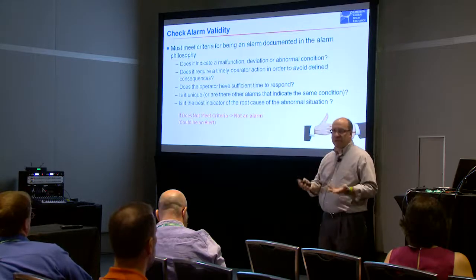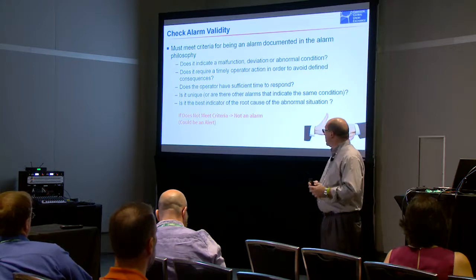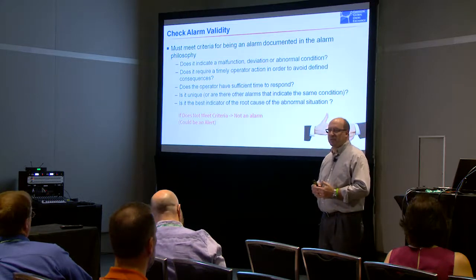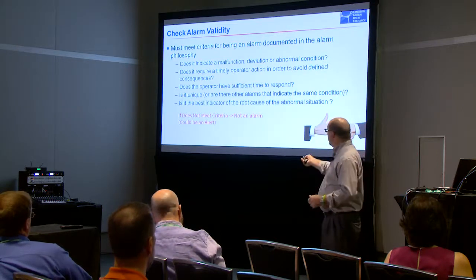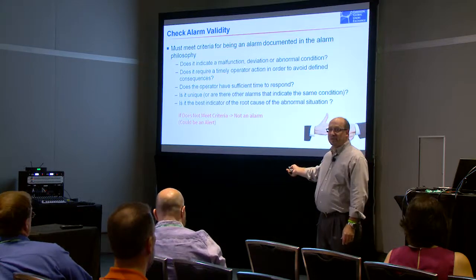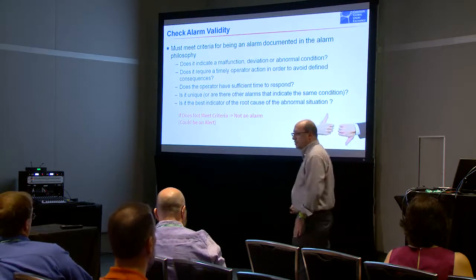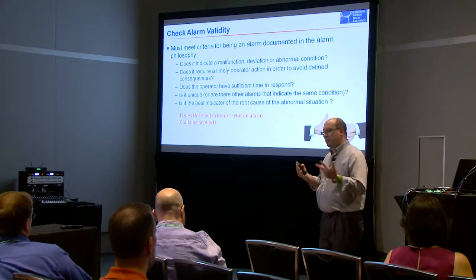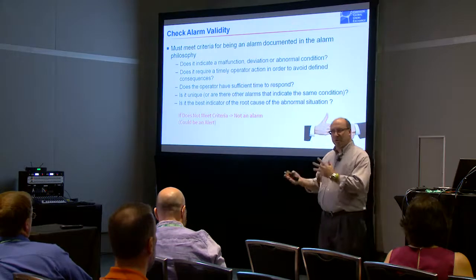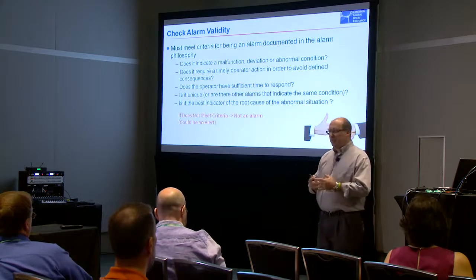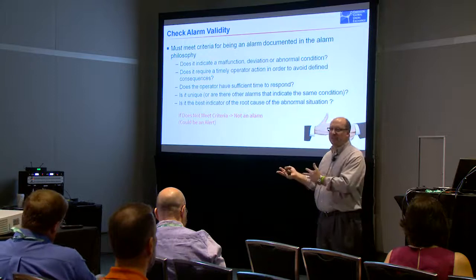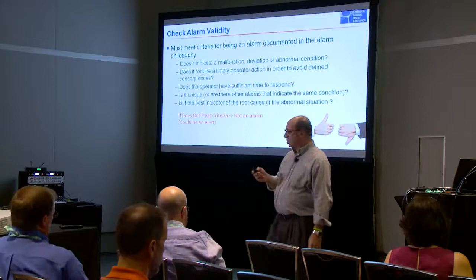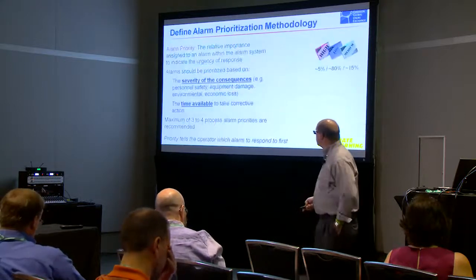Now you can do that during rationalization, but another way to think about it is any time that somebody recommends adding an alarm to your system, before you do it, say, okay, I need you to answer these questions for me. And unless you can answer yes, we're not going to implement this alarm in our system. Because one of the things that you'll find is you can implement a good program for alarm management, but additions, adding a new piece of instrumentation, stuff can sneak in that way because it doesn't go through your full normal alarm management process. So you always want to make sure you're applying this criteria.